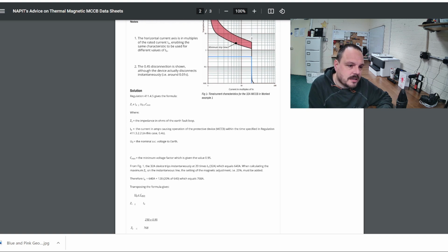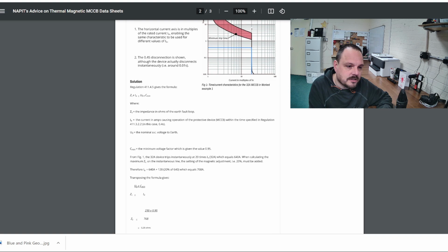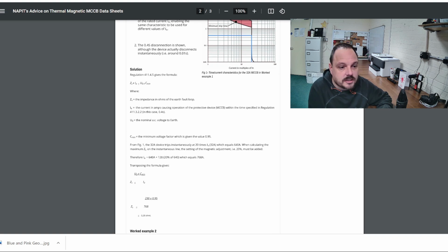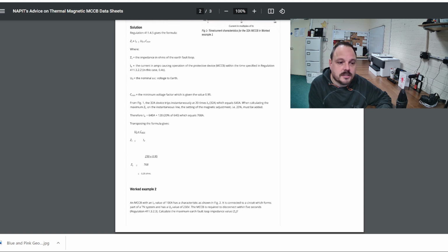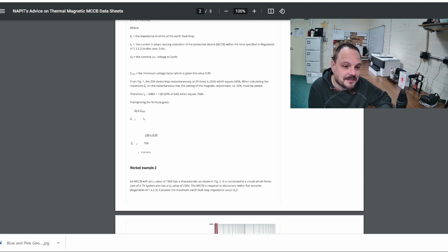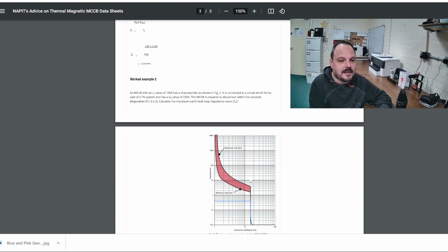But it shows you how to do that calculation. It is basically just transposing the formula, so you end up with your 640 amps, so 20 times the 32 amp rating of the MCCB. Then you've got your 20% tolerance to add on to that, so 128, and you come to the figure of 768 amps. So if you take your voltage, times it by the Cmin, and then divide it by that figure, you get your maximum value of earth loop impedance for that setup on the product.